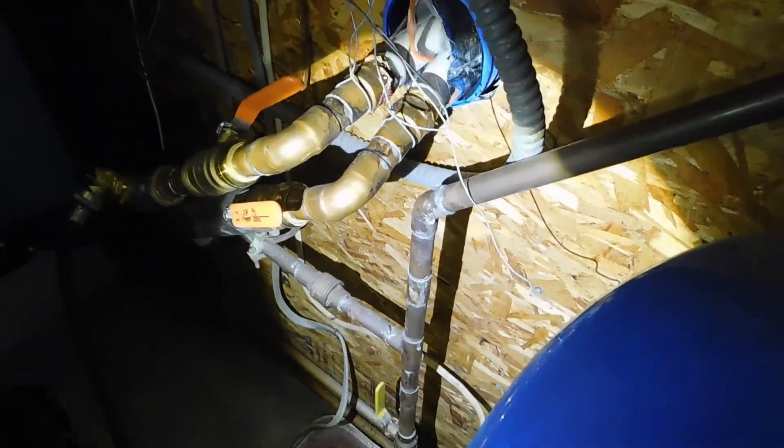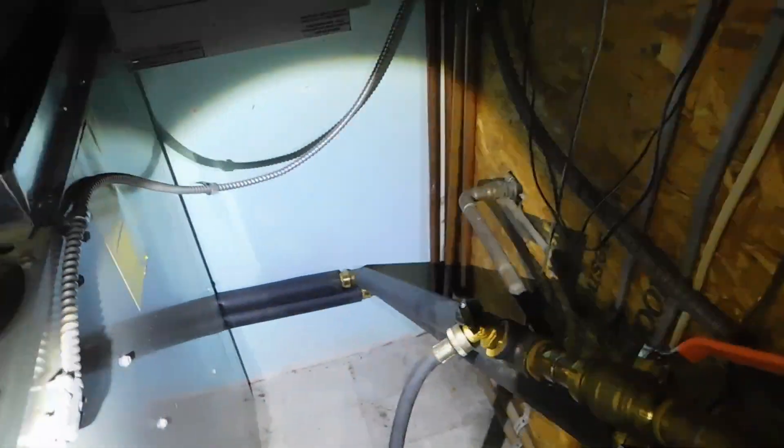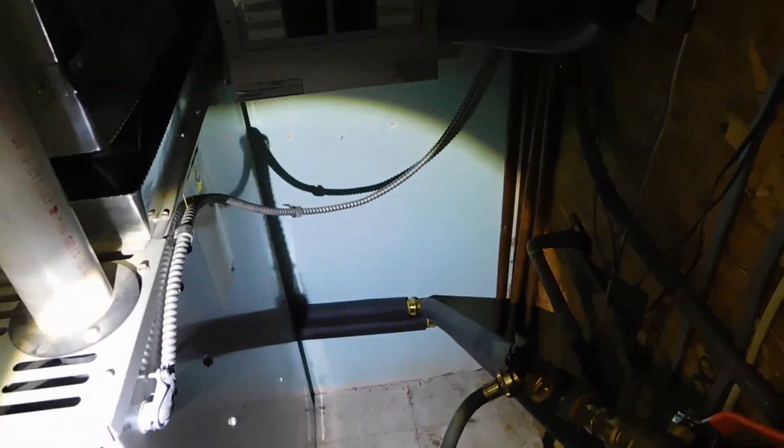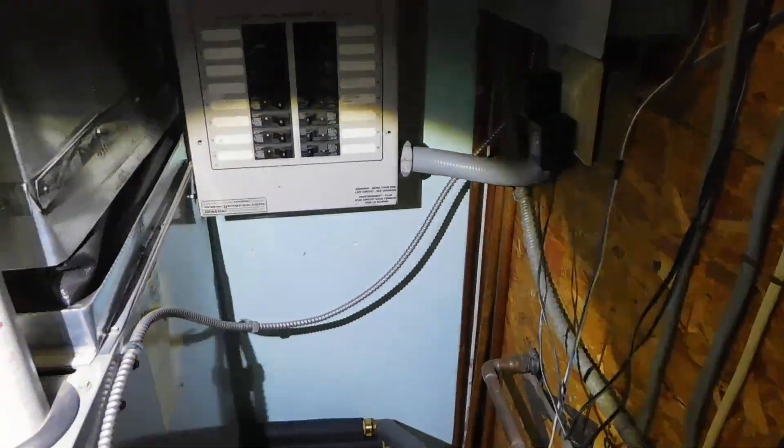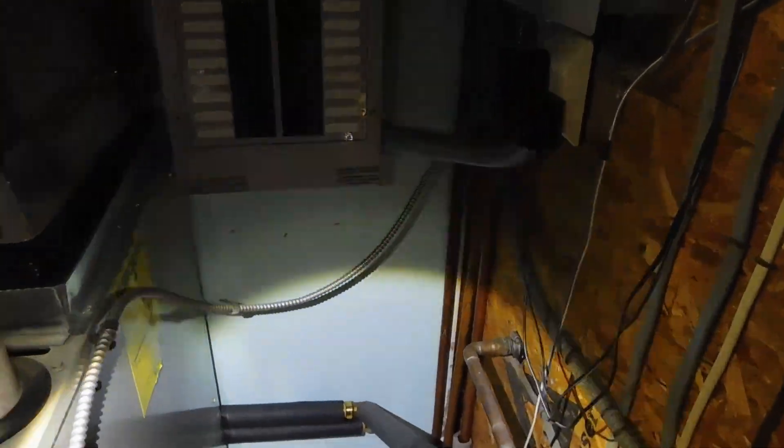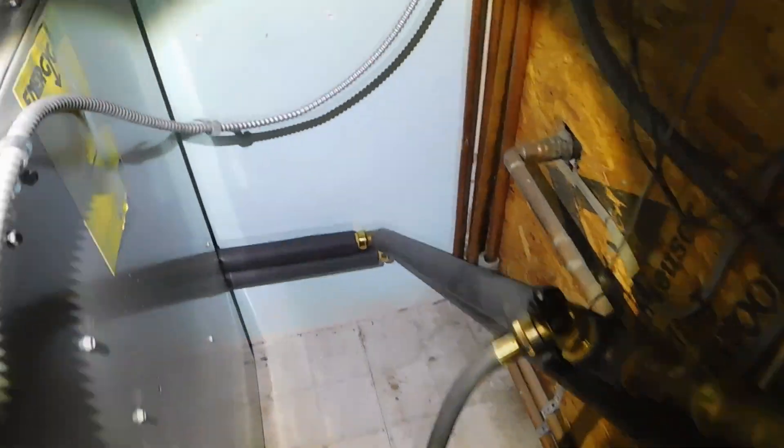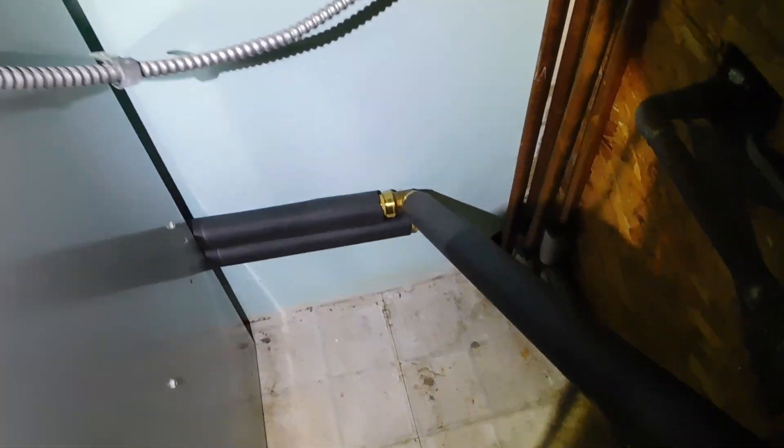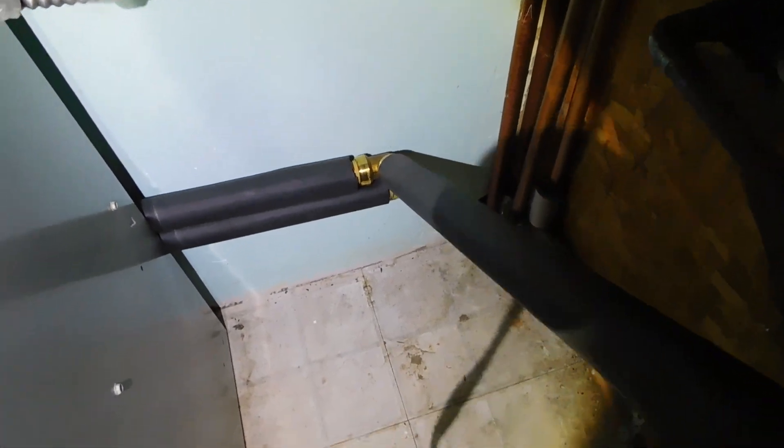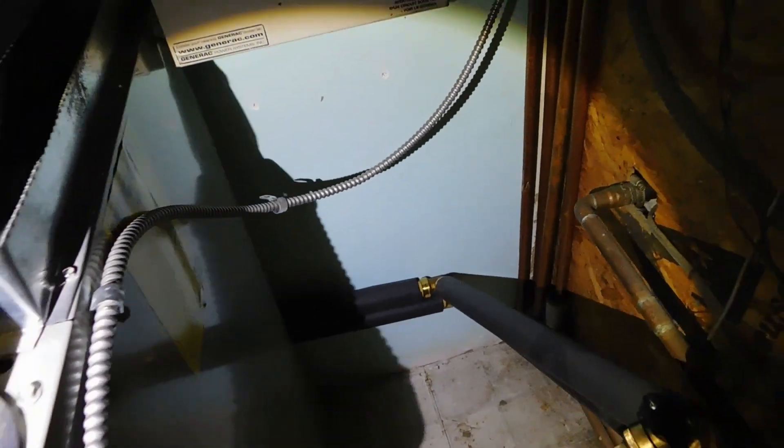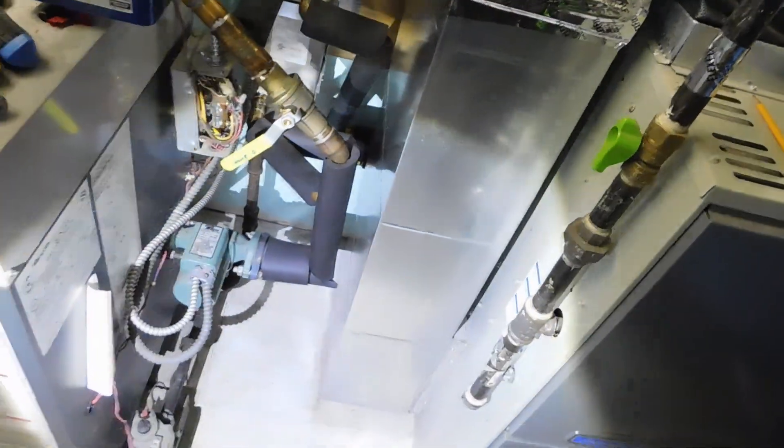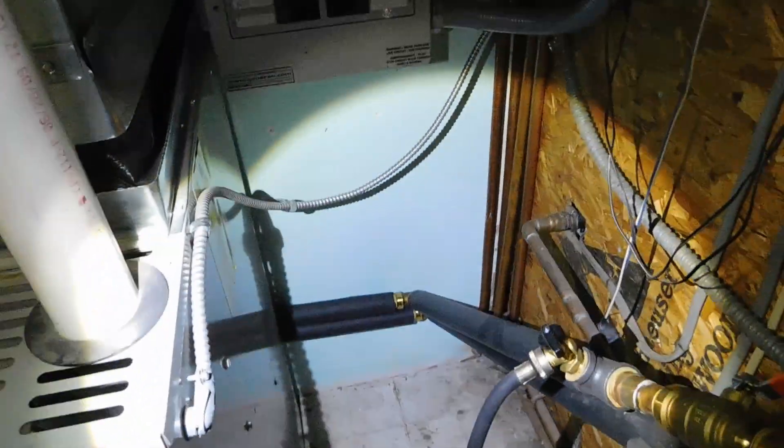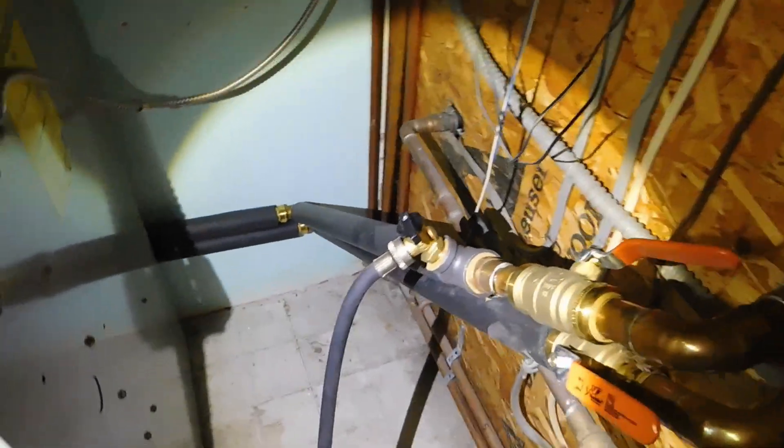Anyway, so my supply and return line, supply's on the bottom, and since this furnace was installed after the fact, it's a very tight fit back here. And I really wanted to solder all these joints in, but there was just no way. I actually soldered a piece together and slipped it behind there, but I couldn't get it to fit all the way from one side to the other, so I ended up going with the SharkBites. This is one-inch copper feeding the plate exchanger.